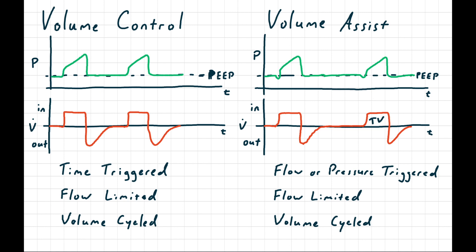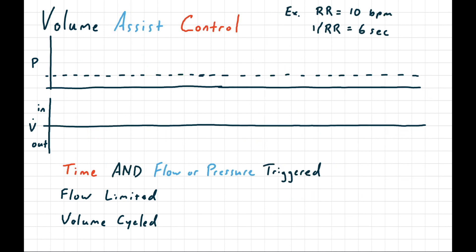In real life, you'll almost never see a pure assist mode. Instead, you'll see assist control modes. Assist control means the ventilator will have a flow or pressure trigger to detect patient-initiated breaths, but there's also a respiratory rate-based timer trigger that will start a breath if the patient doesn't initiate one.